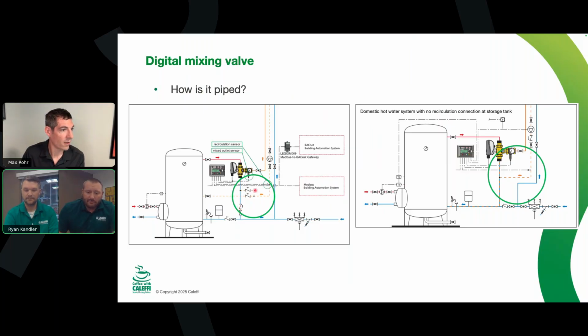Yeah, that's the most important part, I think, is that in this green circled area over here, we actually have 3 different check valves. So we have the recirc line coming back. We want to make sure it can get to the tank. If the cold port is open in the mixing valve, we want that to go right back out to the building. And if it's still warm, if it left at 113 and it came back at 112, this might be full open to the cold, and just let it go back out for another lap. And only when it cools does it crack open the hot port a little bit.